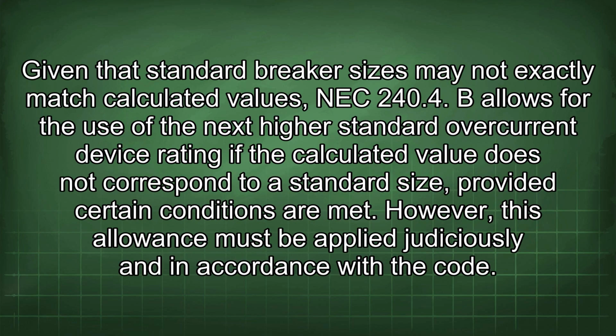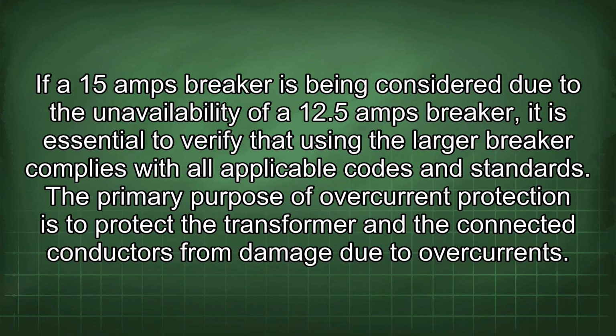Given that standard breaker sizes may not exactly match calculated values, NEC 240.4(B) allows for the use of the next higher standard overcurrent device rating if the calculated value does not correspond to a standard size, provided certain conditions are met. However, this allowance must be applied judiciously and in accordance with the code. If a 15 amps breaker is being considered due to the unavailability of a 12.5 amps breaker, it is essential to verify that using the larger breaker complies with all applicable codes and standards.